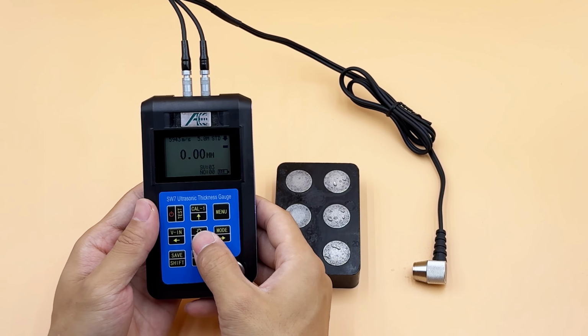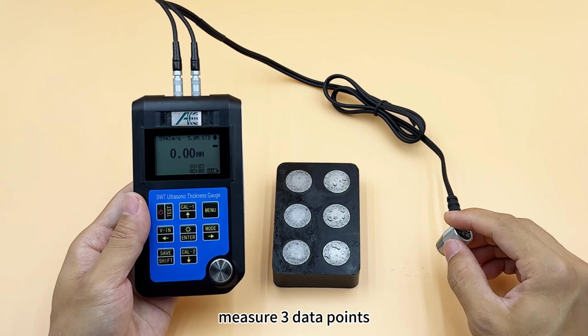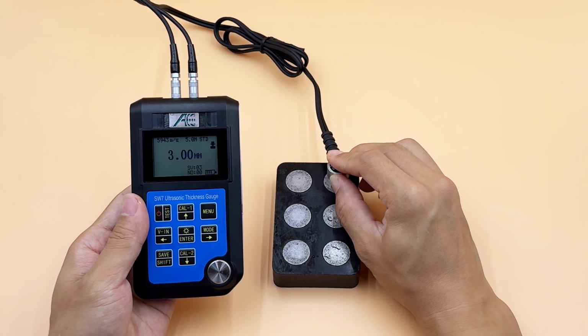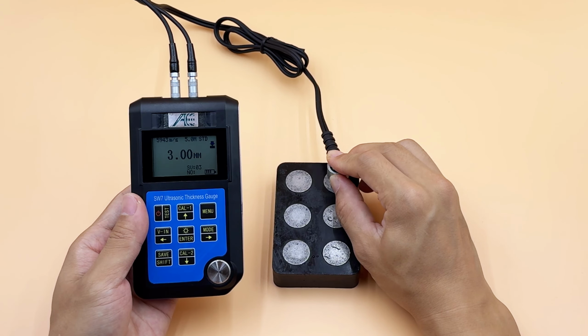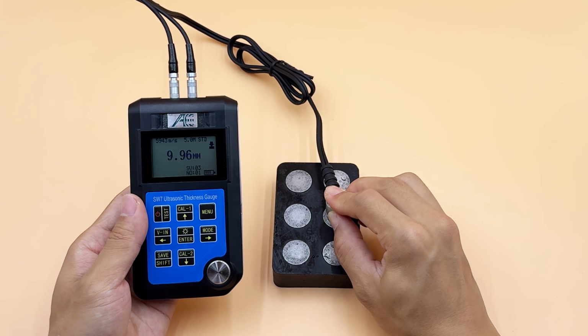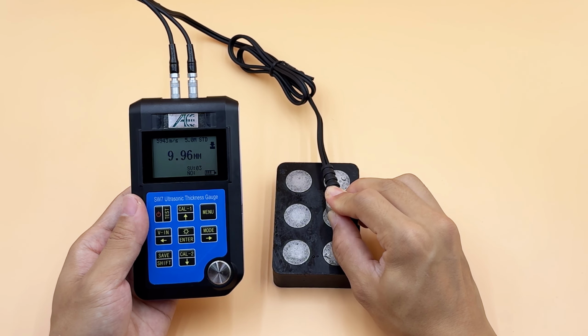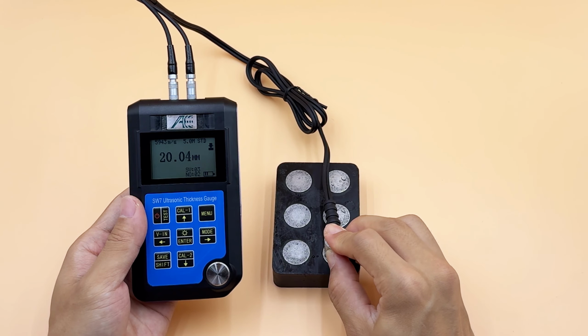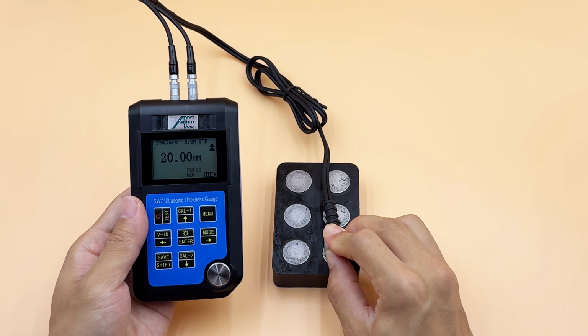Data storage. Press Menu. Select Save, press Enter. Choose Save Set, and enter the number of data point per group. Here, we select 3, then press Enter key. Press Test button. Measure 3 data points. To view the data, press Menu, select Save, check. The stored data will then be displayed.